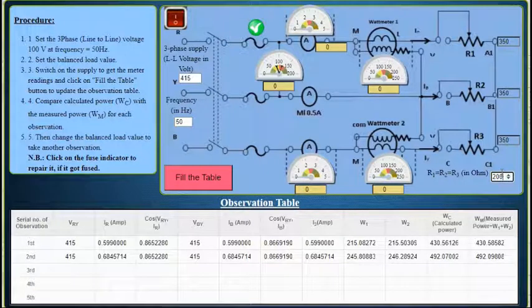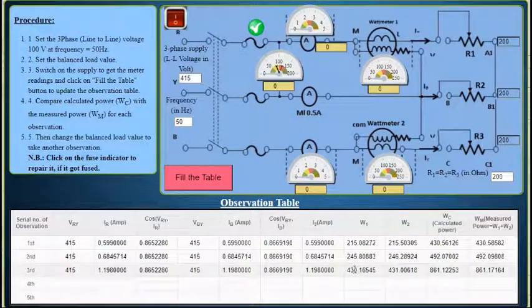Now again you increase the load. Note down the reading: 415 volt. Current is increased to 1.19 ampere. And W1 is 430, W2 is 431. And the total power consumed by the system is 861. So likewise you can vary the load and note down the voltage, current and W1 and W2 readings. From that you can calculate the power factor and the required values.